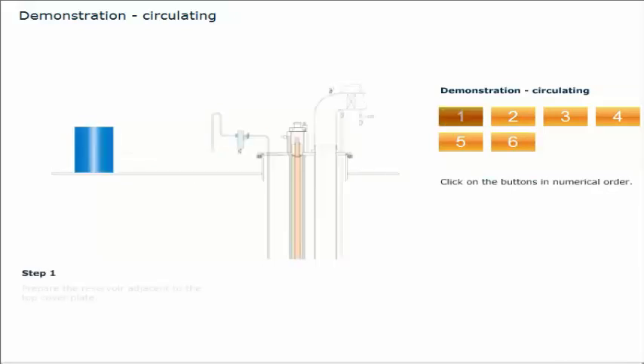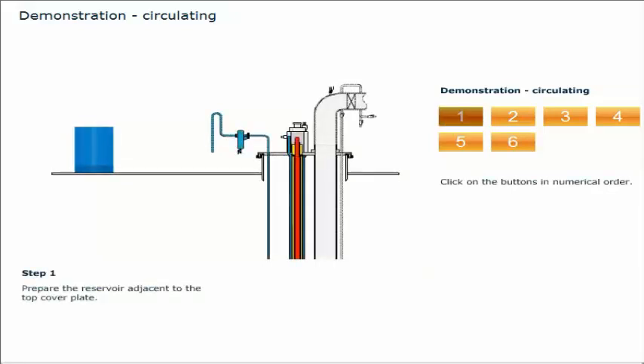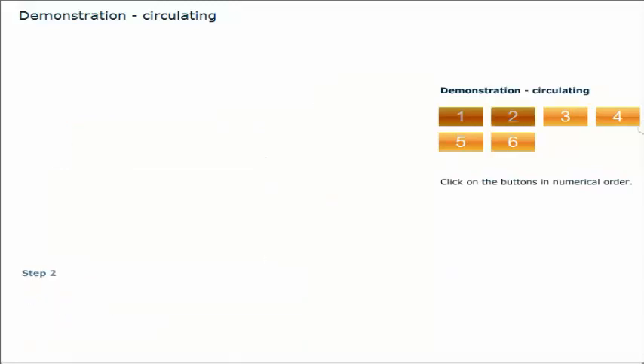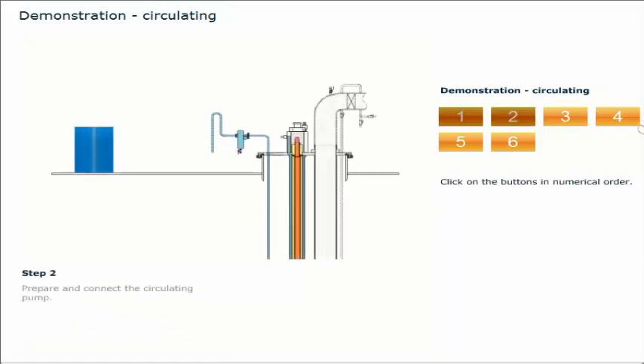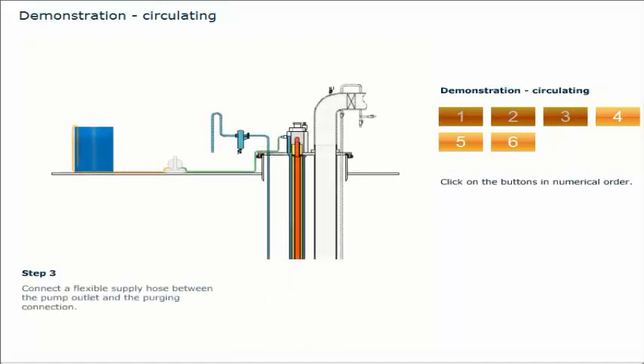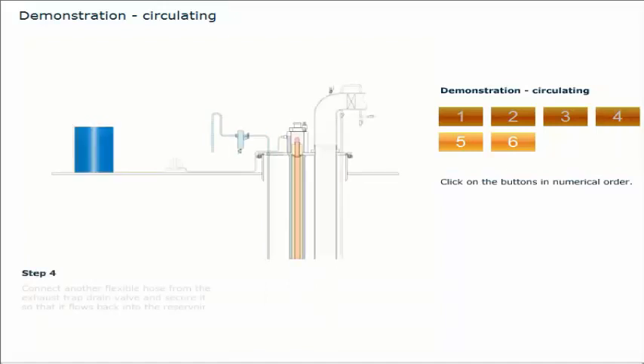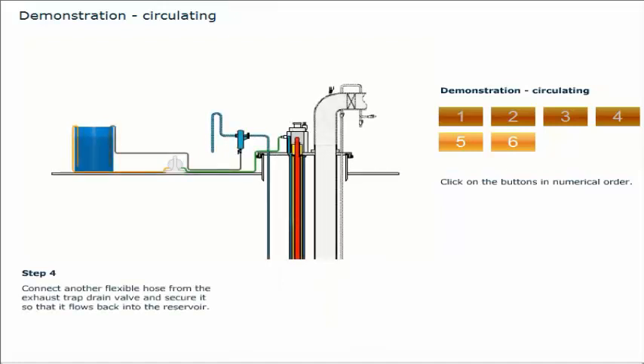Prepare the reservoir adjacent to the top cover plate. Fill with the required liquid. Add heating facility if necessary. Prepare and connect the circulating pump. Connect a flexible supply hose between the pump outlet and the purging connection. Connect another flexible hose from the exhaust trap drain valve and secure it, so that it flows back into the reservoir.